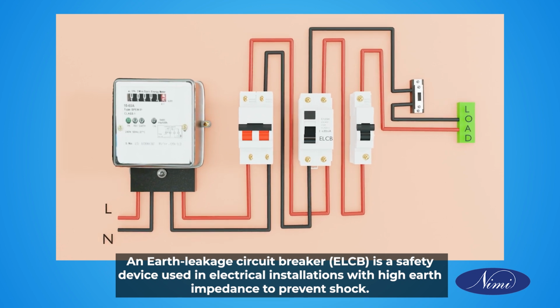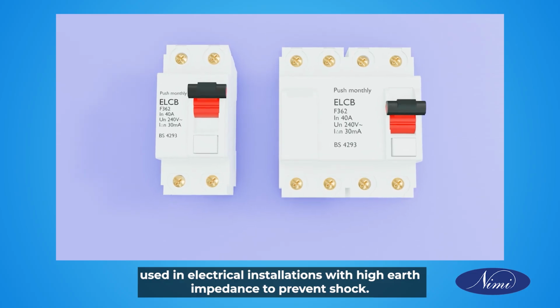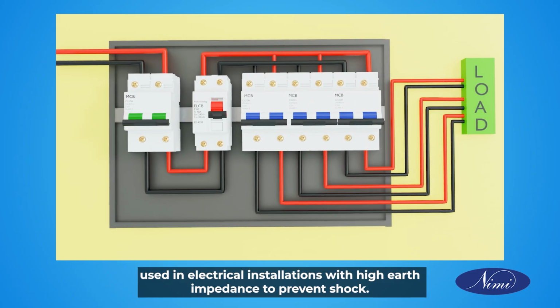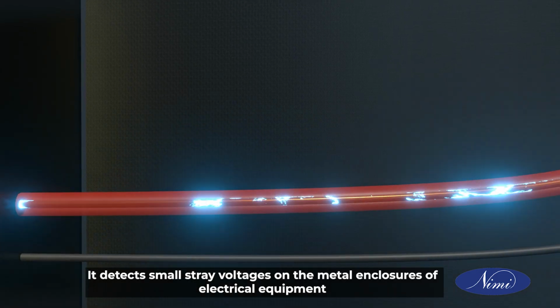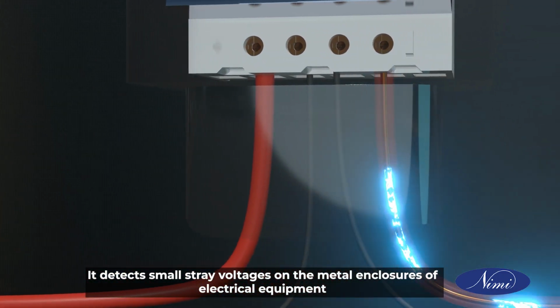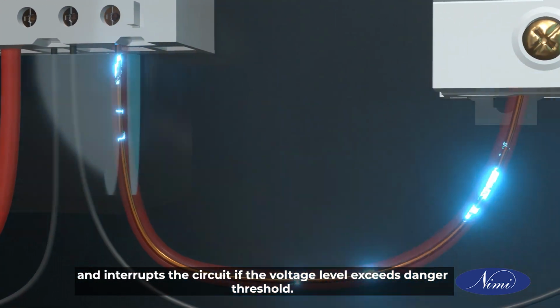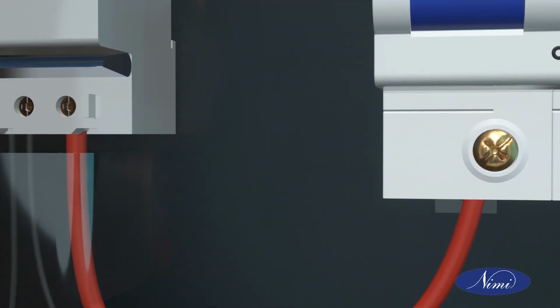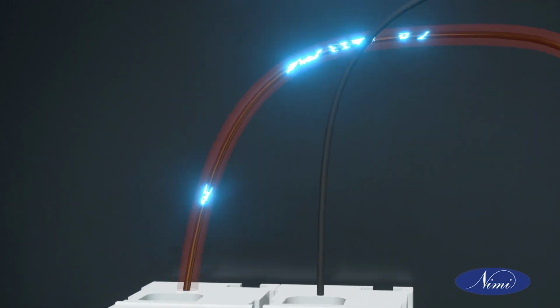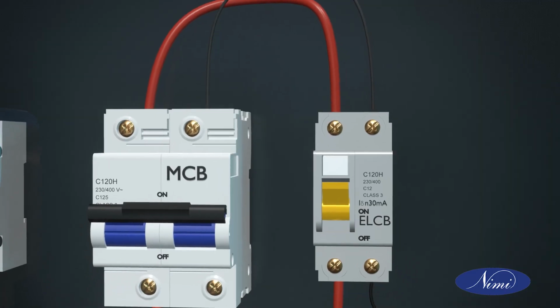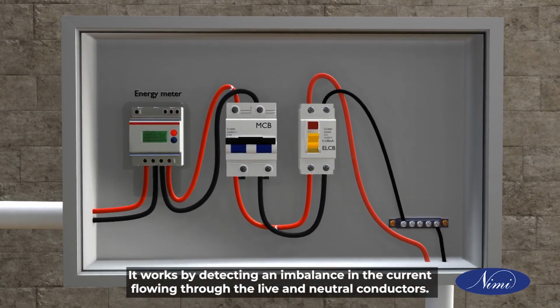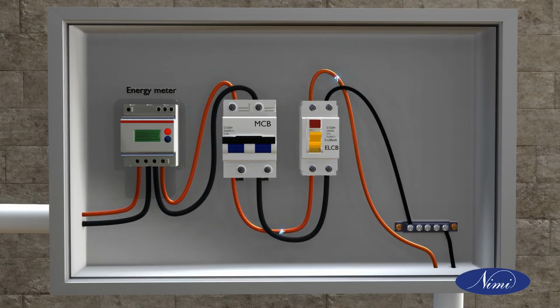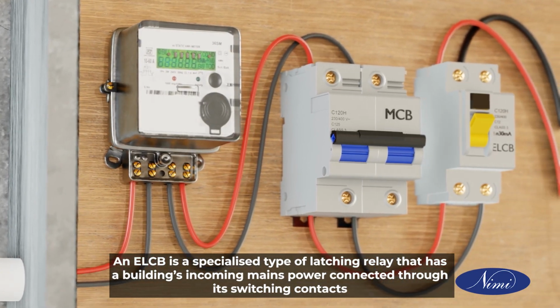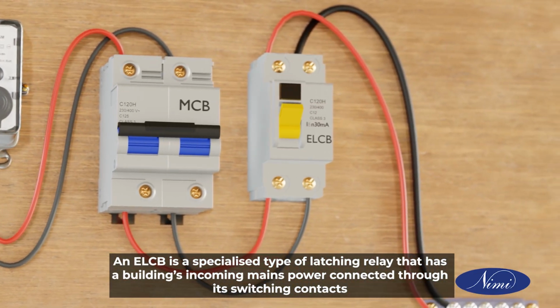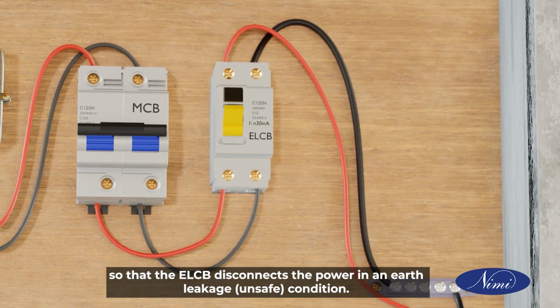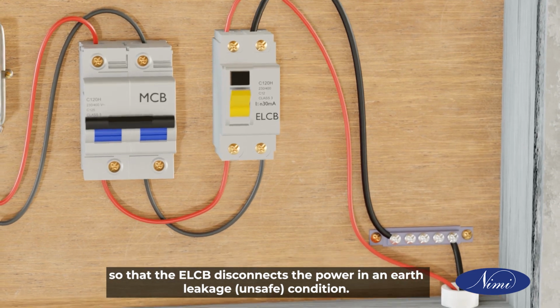An earth leakage circuit breaker (ELCB) is a safety device used in electrical installations with high earth impedance to prevent shock. It detects small stray voltages on the metal enclosures of electrical equipment and interrupts the circuit if the voltage level exceeds danger threshold. It works by detecting an imbalance in the current flowing through the live and neutral conductors. An ELCB is a specialized type of latching relay that has a building's incoming mains power connected through its switching contacts so that the ELCB disconnects the power in an earth leakage, unsafe condition.